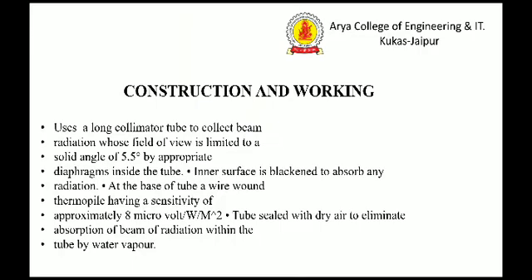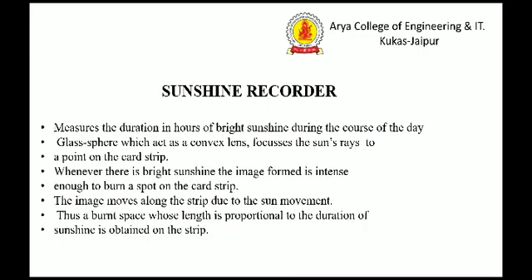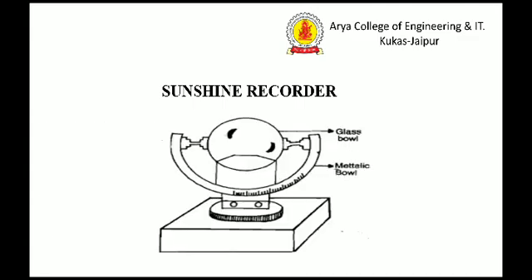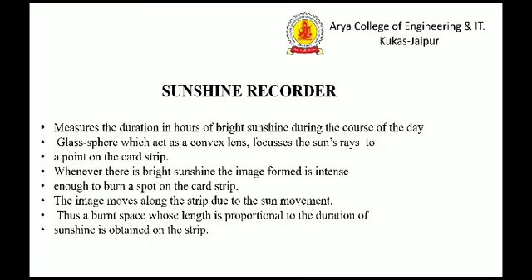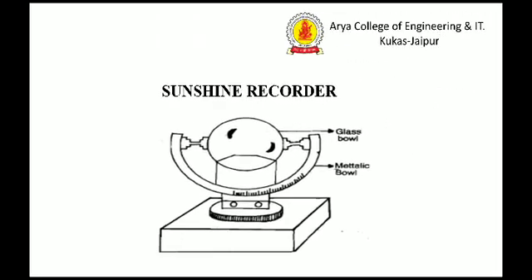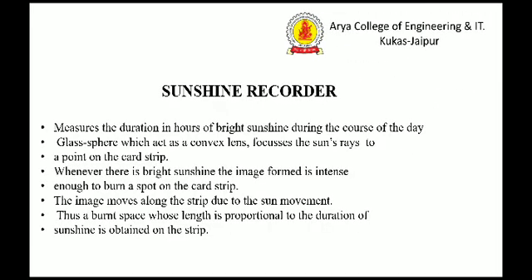The sunshine recorder measures the duration in hours of bright sunshine during the course of the day. A glass sphere acts as a convex lens to focus the sun's rays to a point on a card strip. Whenever there is bright sunshine, the image formed is intense enough to burn a spot on the card strip. The image moves along the strip due to the Sun's movement, creating a burnt trace whose length is proportional to the duration of sunshine.